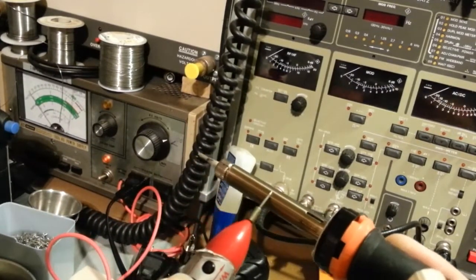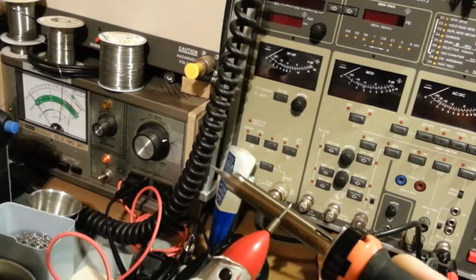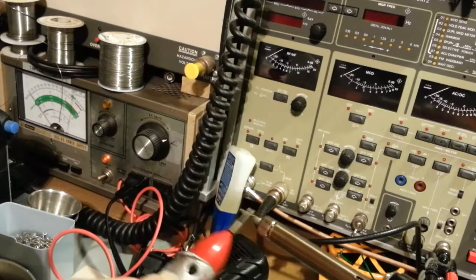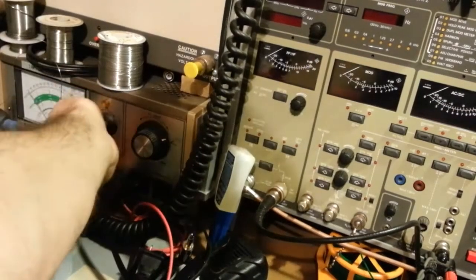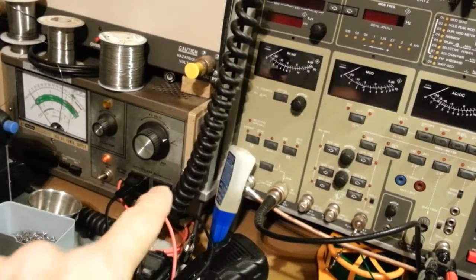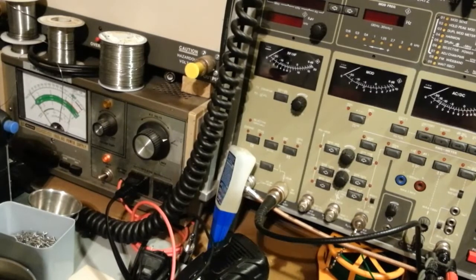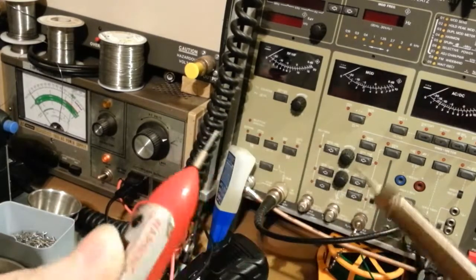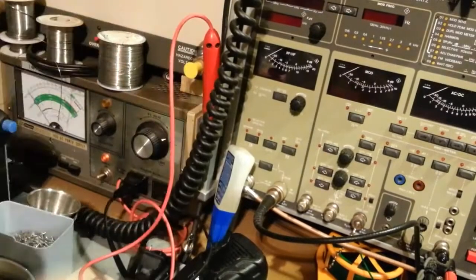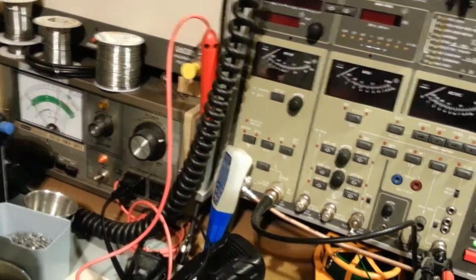So we'll grab the leakage probe here, push the button, and the needle's not moving at all. Not seeing any leakage at all. That's a good thing. Switch over to the common. So what you're doing is you can actually check leakage at the hot and the common leads. There is a tiny deflection of the needle. I doubt you can see that on camera. The needle is probably moving a half of a needle width. That's not even worth writing home about, which means safe. That's a good thing. As long as it's below 500 microamps, we're safe. Well, it's barely a needle width in movement, so that's good.